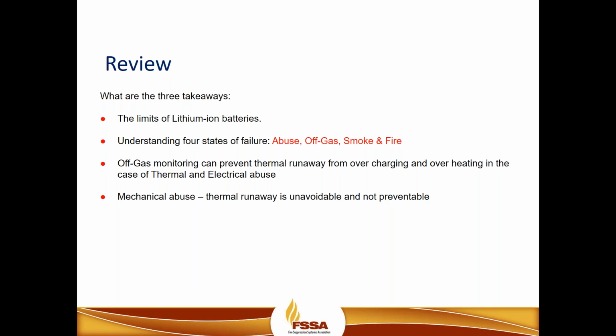So in review, some of the takeaways from today's presentation, of course, lithium-ion batteries do have limitations. They're relatively fragile. They need to be protected. They need to have temperature monitoring. And we need to understand the 4 stages at which battery failure occurs. Stage 1 is the abuse factor. Stage 2 is the off-gas. And that's the critical time, the golden time, where we need off-gas monitoring and early warning detection. And then, of course, stage 3 and stage 4, where smoke and fire is occurring.